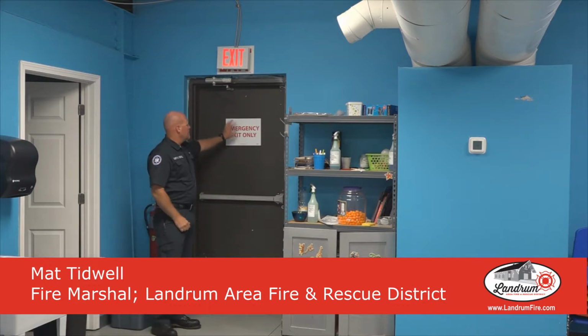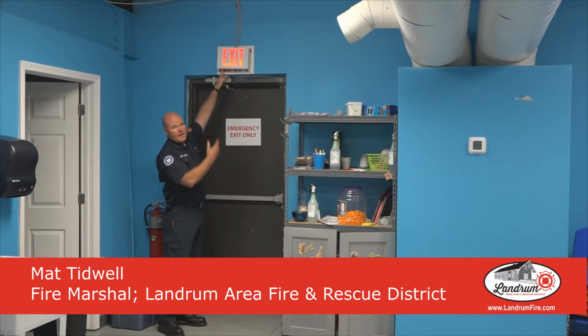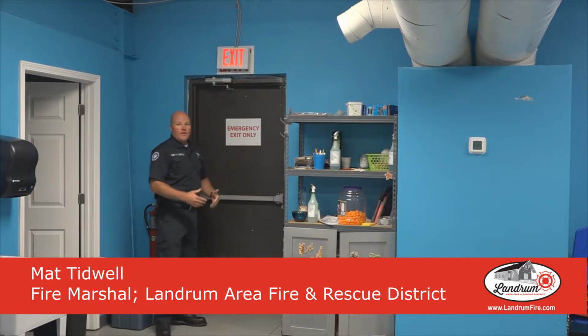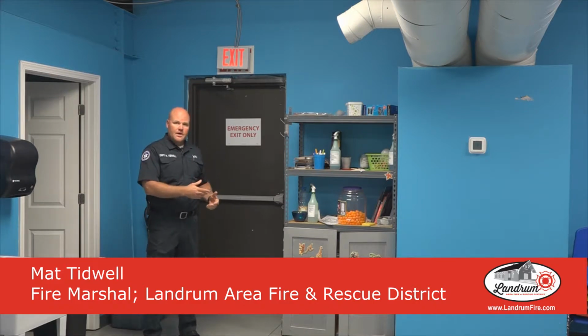Also moving up, emergency exit sign, great. Behind this new one, we have just a printed exit sign. What they've done, we suggested 2 years ago on inspection, they've actually run the electrical exit signs. It's illuminated, and on power failure it lights up. So they have taken our advice on spending a little extra money to make you as a person safer in this structure.